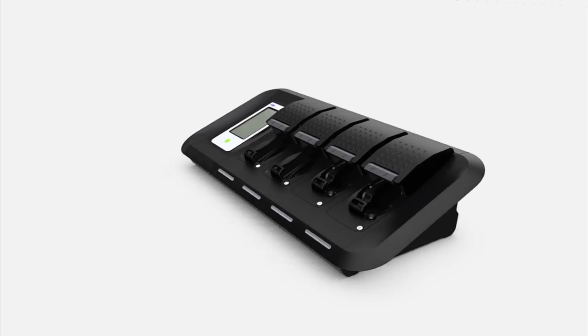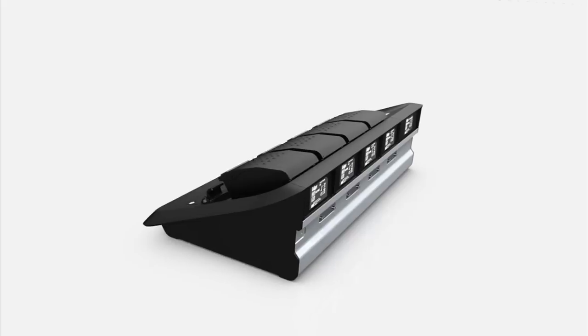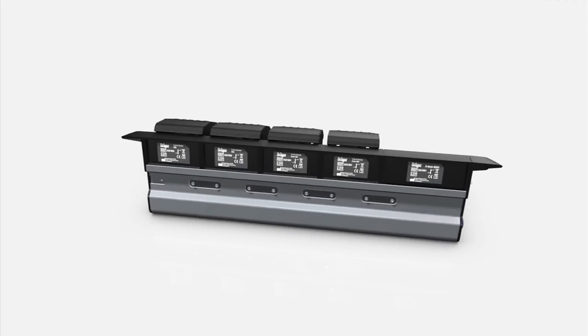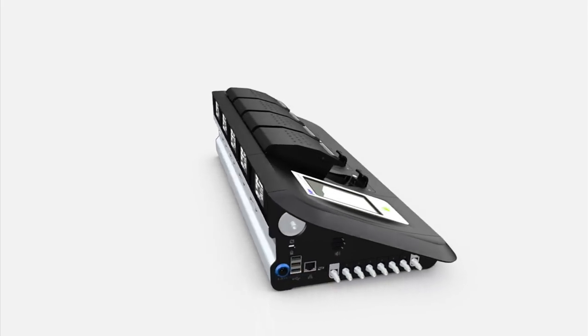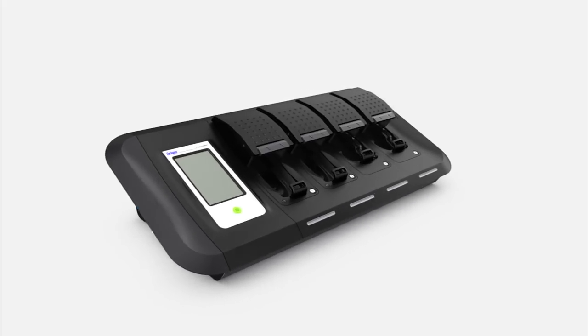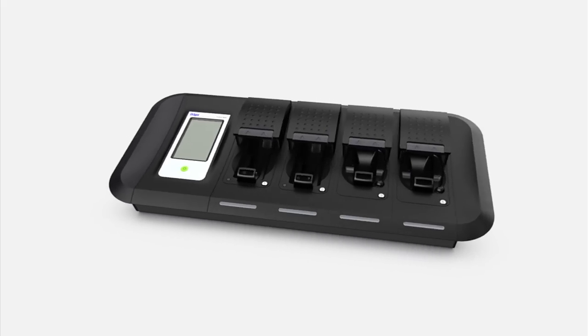The service interval for the Dräger X-dock is 1 year. The maintenance of the entire station should be performed by specialists. Dräger recommends contacting the Dräger service team.